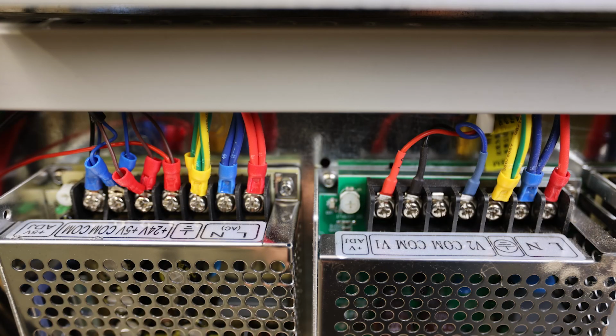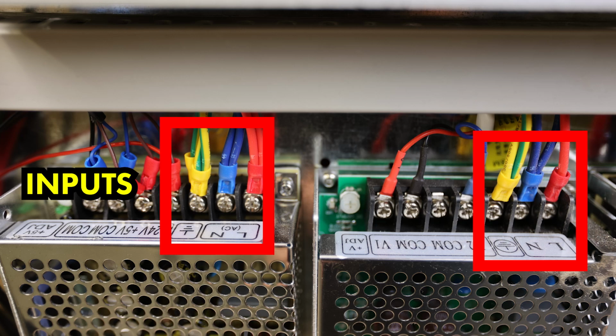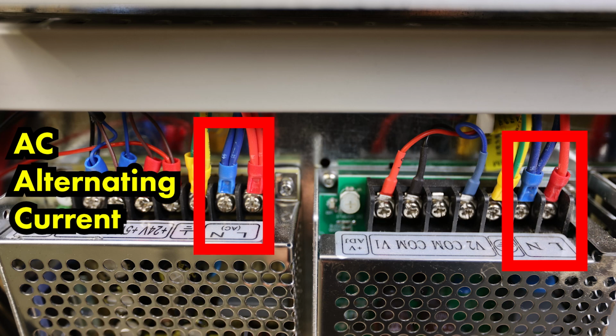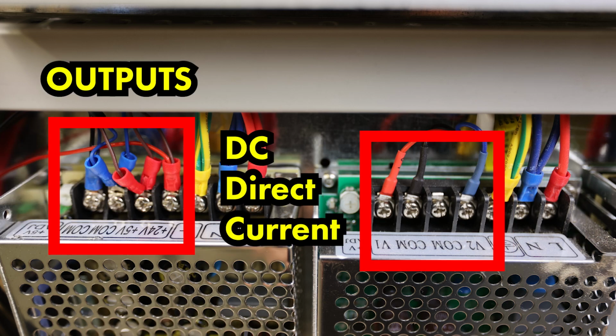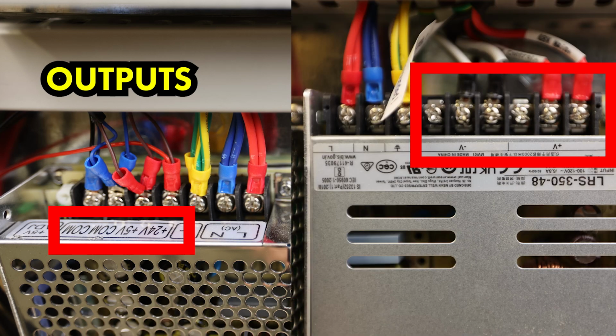Before continuing on to the voltage section of the video, we should first cover the basic anatomy of our power supplies. We will always have 3 terminals labeled line, neutral, and ground. The line and neutral terminals are where the power supply receives power from the wall in the form of AC, or alternating current. The other terminals will be our output terminals, which will supply their assigned voltage as DC, or direct current. There will typically be positive and negative output terminals. Sometimes instead of a negative output terminal, you'll see it listed as COM, or common. For the purposes of this video, negative voltage output terminals and common output terminals can be considered the same.